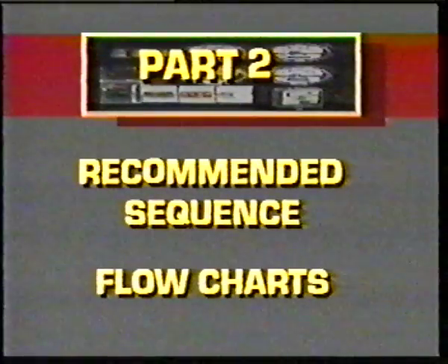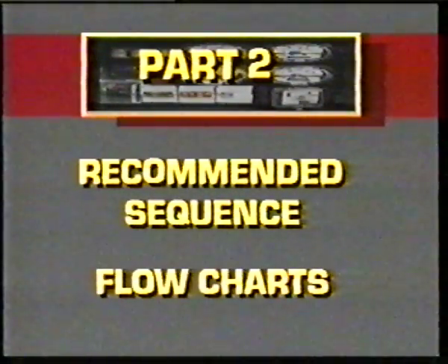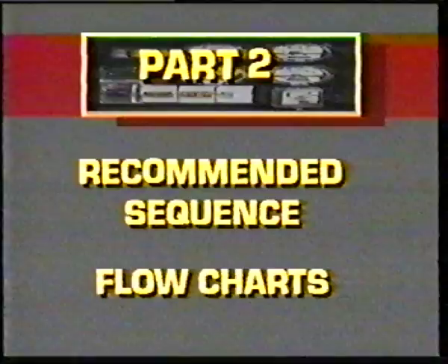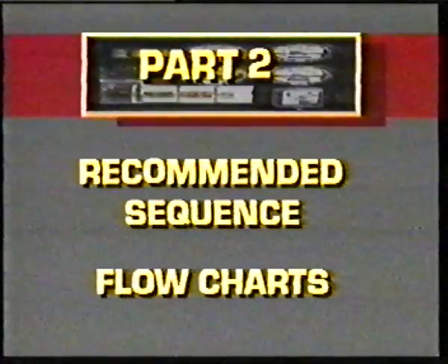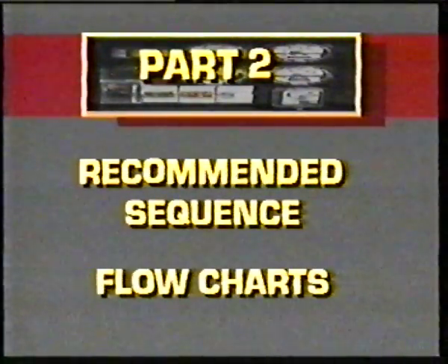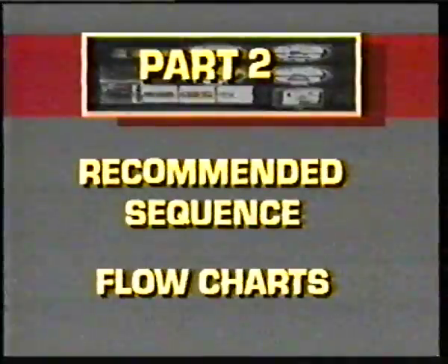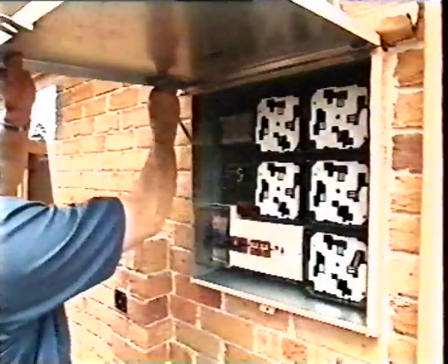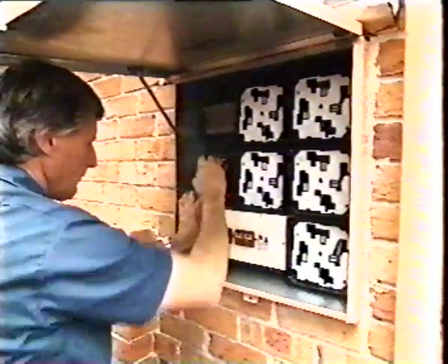In order to ensure that all required tests are carried out, it's recommended that the sequence of testing should follow this flowchart. Just as with the test methods, a complete domestic installation has been selected. Each test is only covered briefly, and all alternative methods and equipment aren't shown as they were detailed in the first section. Now let's look at the flowchart in detail.